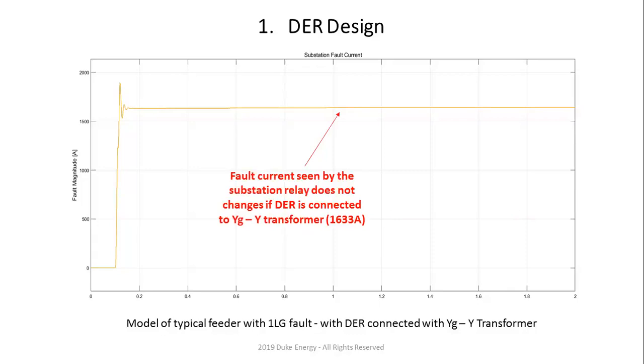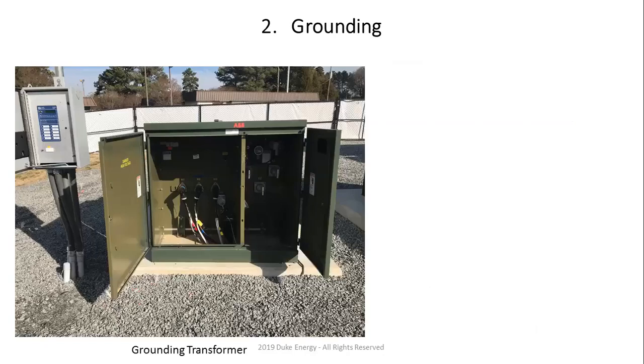And I have seen a lot of designs with this Y grounded delta transformer because it requires an understanding of protection and control. And this also has a major effect on the overvoltages and everything that happens during the faults, right? So that's the first thing. Second thing, grounding transformer, right? So now when you have a Y grounded Y transformer configuration, and if you have distributed energy resources, that means the Y side is not grounded, and that is tied to your PV, to your battery, anything that is inverter based.